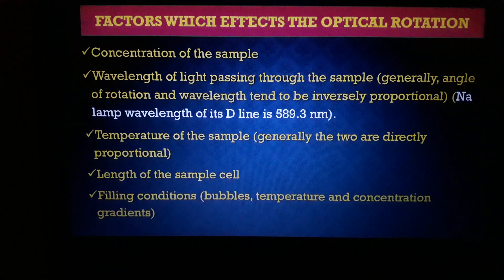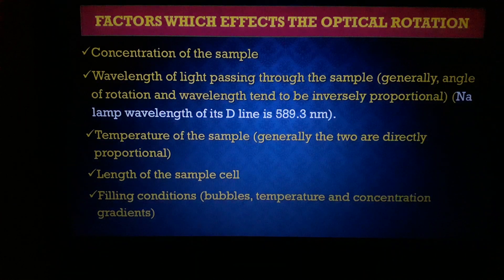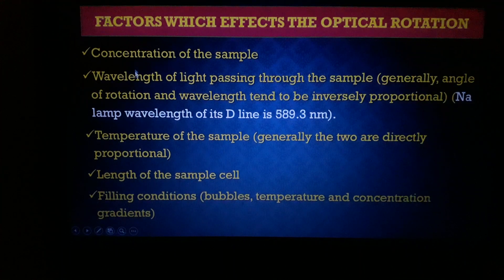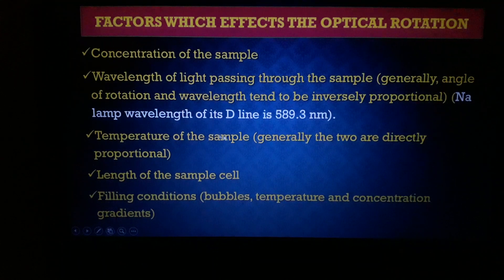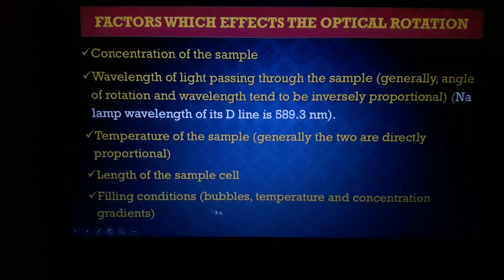Factors affecting optical rotation: concentration of the sample solution — optical rotation is linear with sample concentration. Wavelength — the angle of rotation is inversely proportional to the wavelength; we commonly use the sodium D-line at 589 nm. Temperature — directly proportional to optical rotation; higher temperature gives more rotation. Length of the sample cell — this also impacts optical rotation. Filling conditions — the sample tube must be filled with a clear, bubble-free solution.